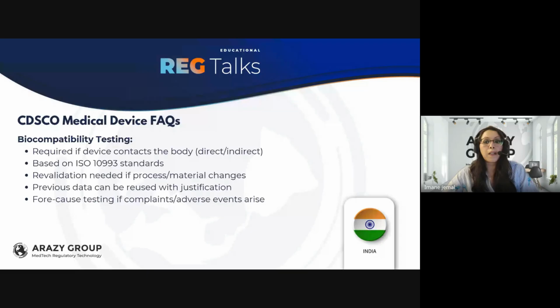If you have already done it for a similar device and the material, supplier, and process are the same, you can reuse that data with proper justification and biological risk assessment. But if there is any change in, for example, supplier, material, or process, you must revalidate. Also, if any complaint or adverse events are reported, the authority would expect fresh for-cause testing. So yes, it's mandatory where contact exists, but CDSCO is also being practical about avoiding duplicate testing. This is regarding the biocompatibility testing.